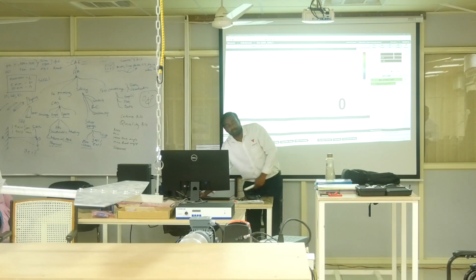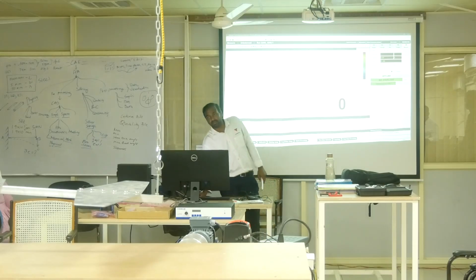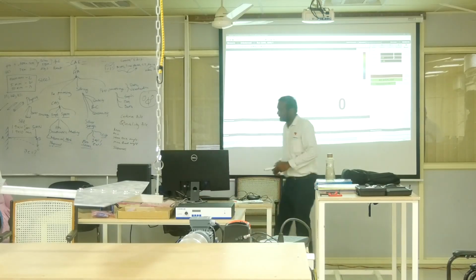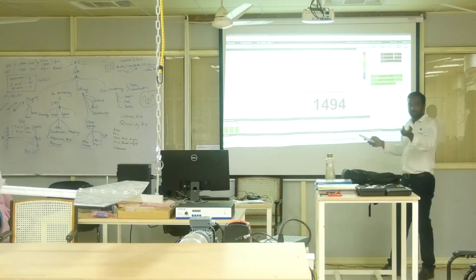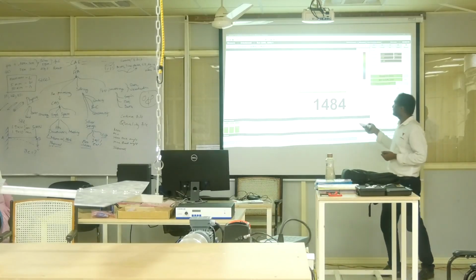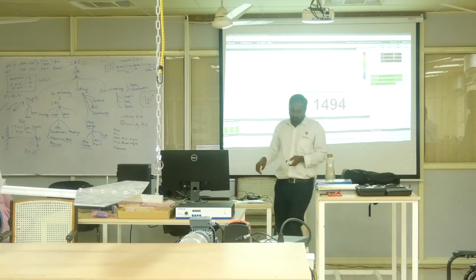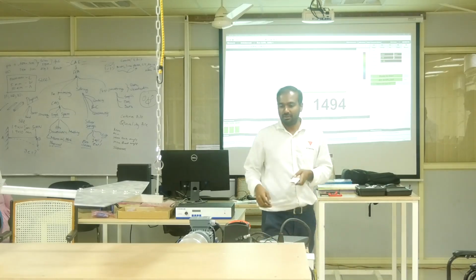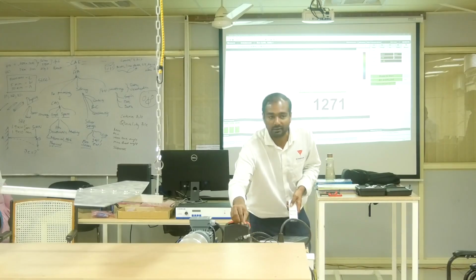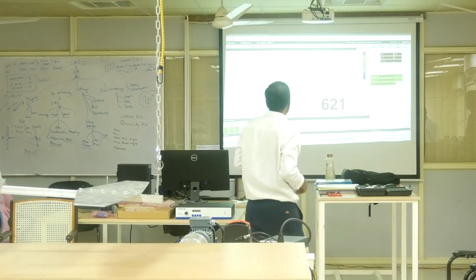So this is the measure panel tab where we are acquiring the data. Once I click arm the signal, arm the sensor, it is ready for capturing the measurement. So I will reduce it, as I have set it to capture the signal from 300 to 1200 RPM, and start it slowly.